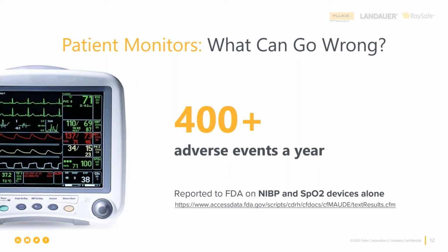intensive care beds. And it's also important to note that medical devices fail, right? So we're talking about how they're being used and why they're important, but it can go wrong even in this day and age. It is becoming increasingly more infrequent, but there's no replacement for good routine preventive maintenance. And as you can see on this slide, the FDA, which is going to be US only data, so think about this number being larger globally, states that there are still 400 plus adverse events a year that relate only to two of the parameters I talked about, just NIBP and SpO2. So it's still something that we need to check. And again, these patient monitors are critical to a correct diagnosis and a correct treatment for these COVID patients.